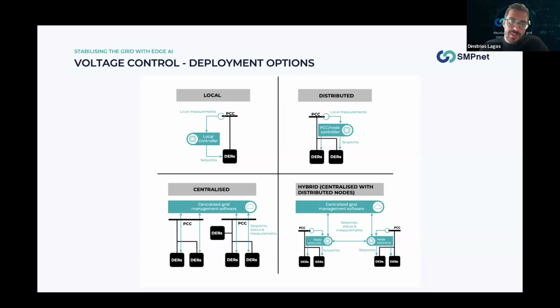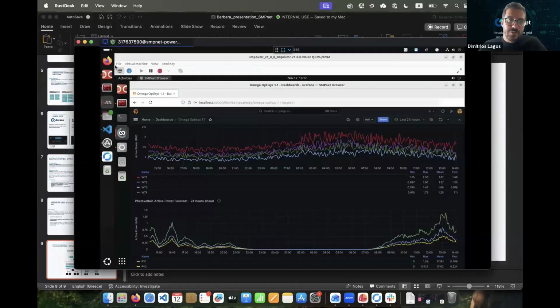So for local or distributed designs, the issue is that you might not get an optimal solution, and you might end up having the local controllers coordinating poorly with one another. In a central solution, you can have an optimal coordination of the DERs, but you end up with a single failure point, the centralized grid management software. So the hybrid approach can combine the benefit of both options. It can have the optimal operation of a centralized grid software and also have the robustness of operation using also local edge devices that can operate in case of a central software failure. So having said that, I can move now to a demo of our solution.